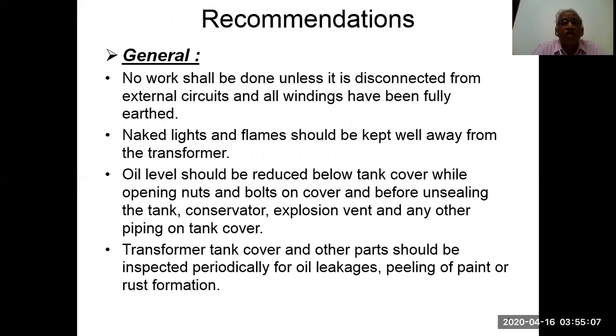Recommendations. General: no work shall be done unless it is disconnected from the external circuits and all windings have been fully earthed. Otherwise, you will have a shock, and this is a precaution. You should be very careful about it. Naked lights and flames should be kept well away from the transformer. Oil level should be reduced below tank cover while opening the nuts and bolts on cover and before unsealing the tank, conservator, explosion vent and any other piping on the tank.